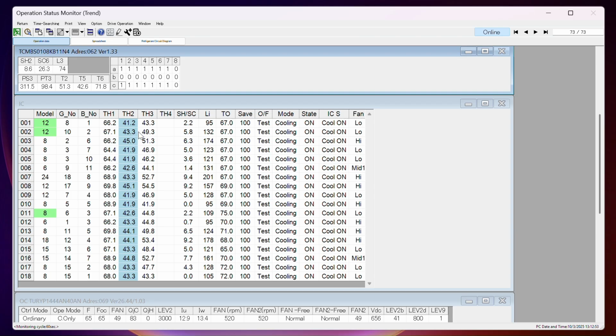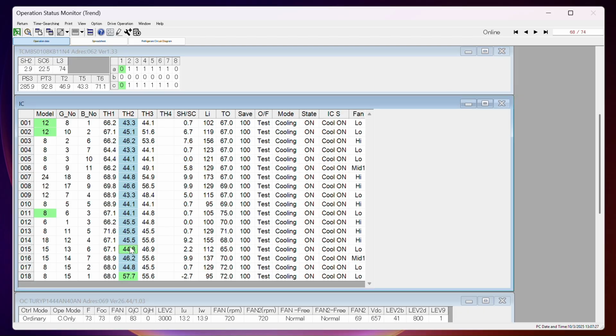Now, one thing I do want to note, if any of these ports had been incorrect, it wouldn't change the speed at which the port verification was going. So let's say, for example, on here, instead of when I closed off 1 on the sub BC, instead of this one losing refrigerant right here, let's say that this device right here lost refrigerant. So this guy. Well, what that would mean is that, okay, I closed port 1. This is set to 6, but it's physically connected to port number 1 on the sub BC. And I know that because, well, I just killed refrigerant on port number 1.